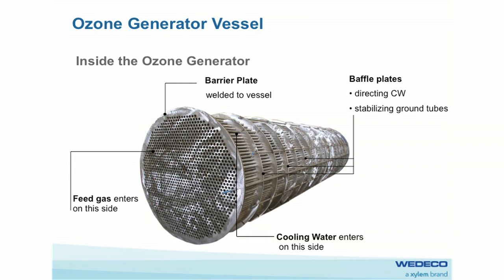The electrodes all go into this side of the generator body. They feed into both sides of the generator body. The outer body is grounded, and you pass about 5,000 volts through each electrode. The whole shell is immersed in water, so you've got very, very good contacting between your cooling water and your electrodes, which is very important because a lot of the energy that's used in creating ozone creates a lot of heat, and heat is detrimental to the whole ozone generating process. So yeah, we have very good heat removal, so our power consumption is very efficient.